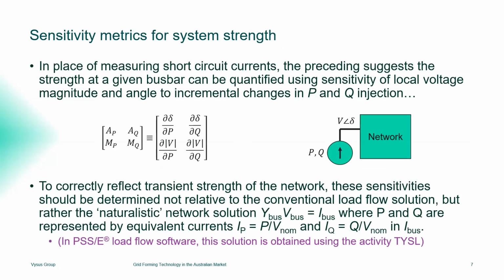So what that has led us to do when we're trying to get quantitative metrics of system strength that don't depend on having fault currents that are determined by passive Ohm's law characteristics of the networks, we can take a different approach. We can actually look directly at the sensitivity of voltage magnitudes and angles in the network to small perturbations in P and Q injection at particular points in the network. So you can imagine that we have a kind of Jacobian matrix here. And so this is just talking about the relative change in voltage magnitudes and voltage angles equivalent to a certain change in P and Q injection at a certain point in the network.